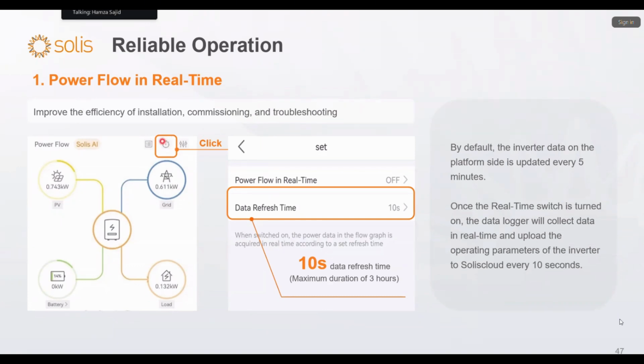So in the Solis app, you can click on this stopwatch, and you can set the real time flow data refreshing rate to 10 seconds for 3 hours, which is equivalent to seeing the load just like real time working. This will help you improve the efficiency of installation, commissioning, and troubleshooting if you are doing the system installation.